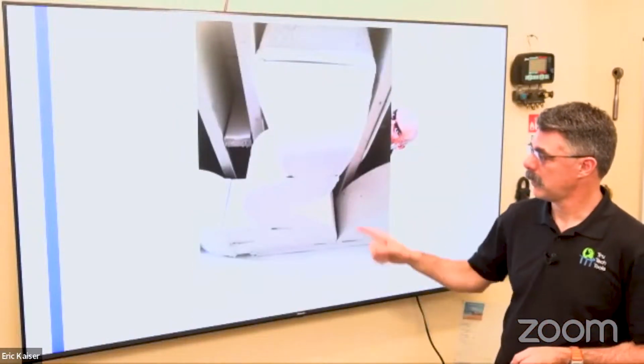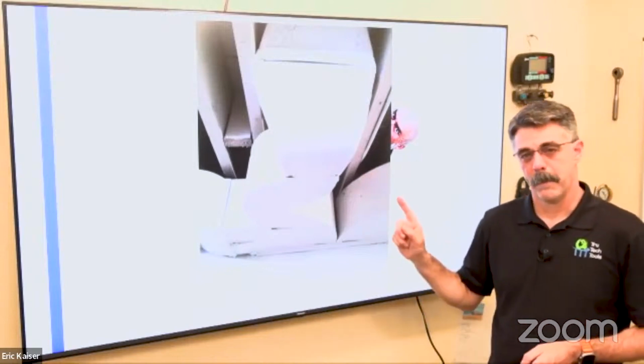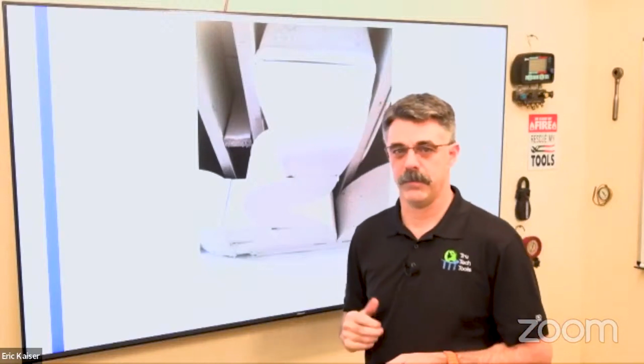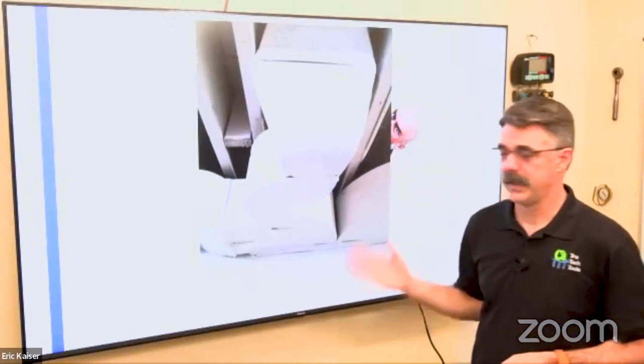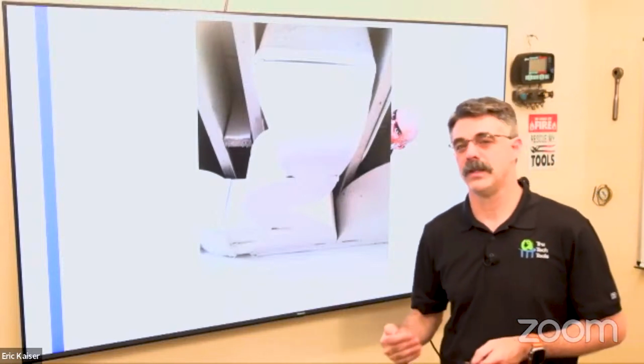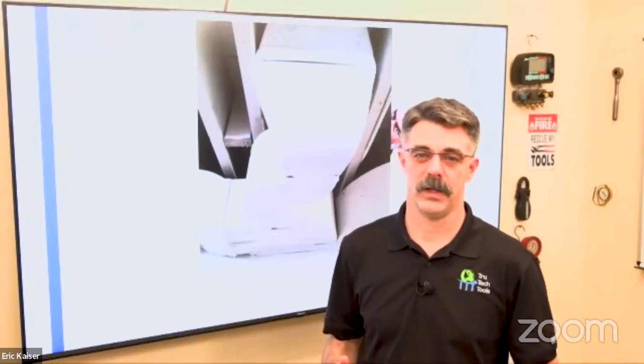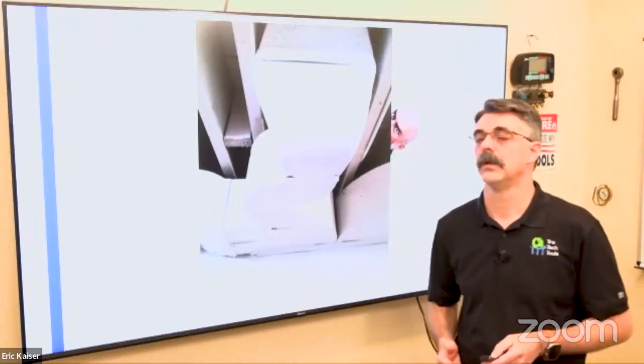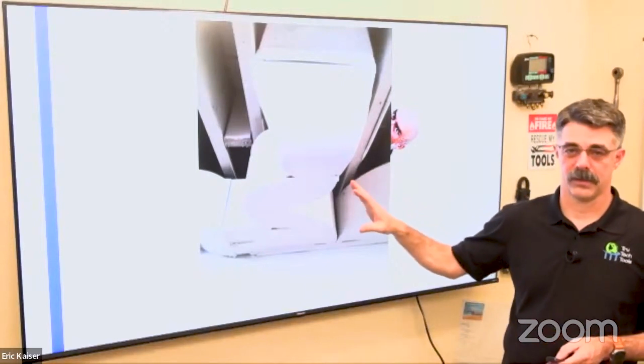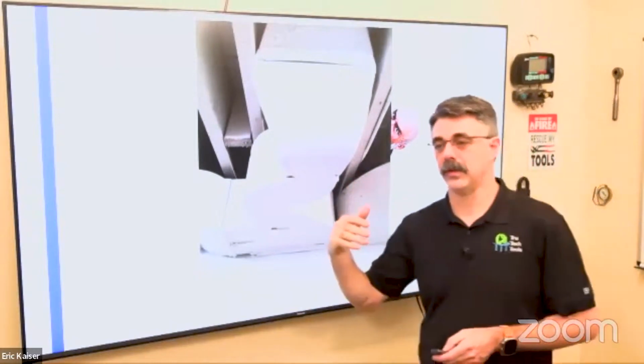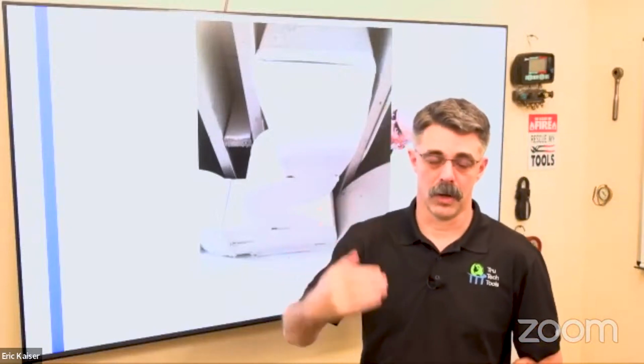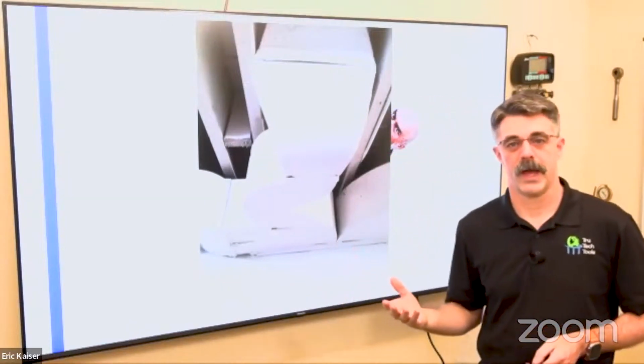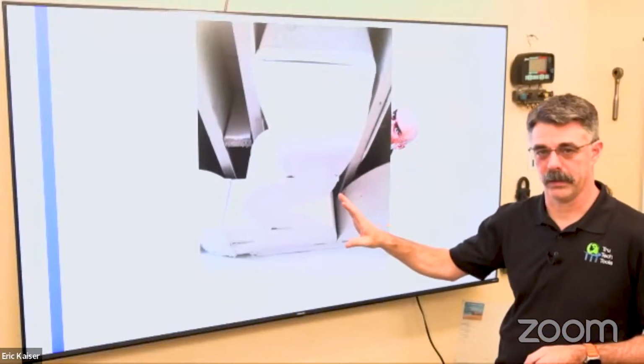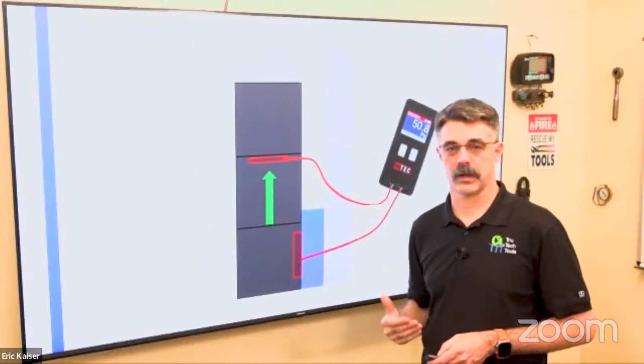All right. Ductwork. We can look at ductwork a lot and we can visually say, okay, we think that's going to work. We think it's not going to work. That's some really pretty sheet metal. But until we test it, we really have no idea whether it's going to work or not. We're either guessing or we're testing. Okay. So there are several ways that we can test this. One of the biggest ways is we need to make sure that the ductwork is large enough for the new equipment that we're going to be putting in there. Once we do that, the equipment at least is going to work well. All right, and the ductwork's not going to kill the equipment.